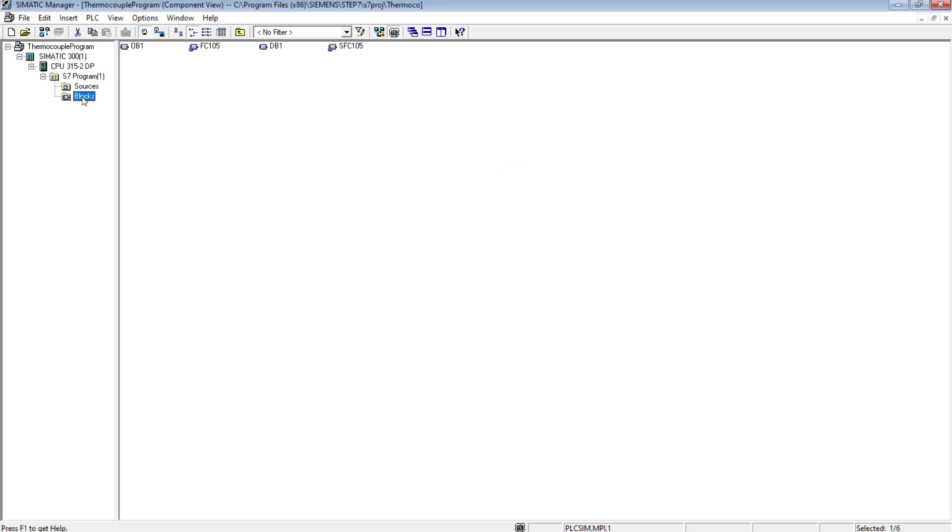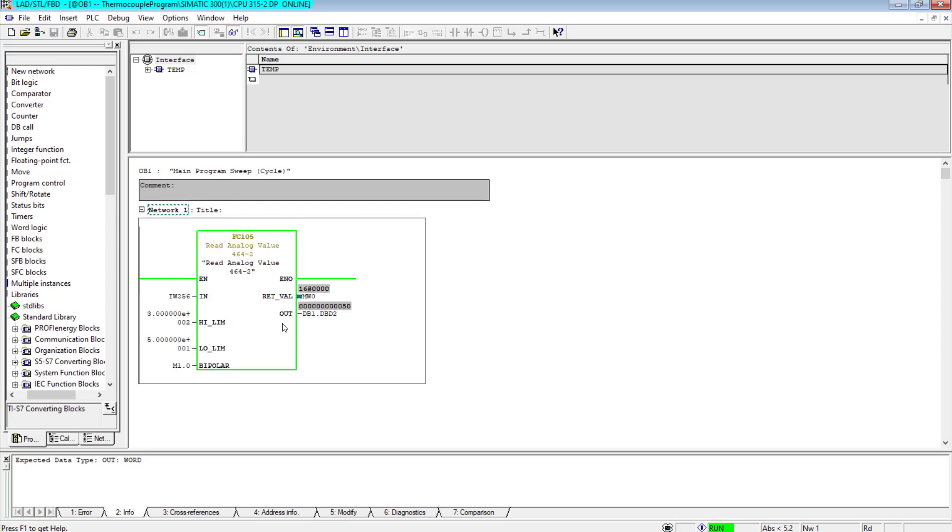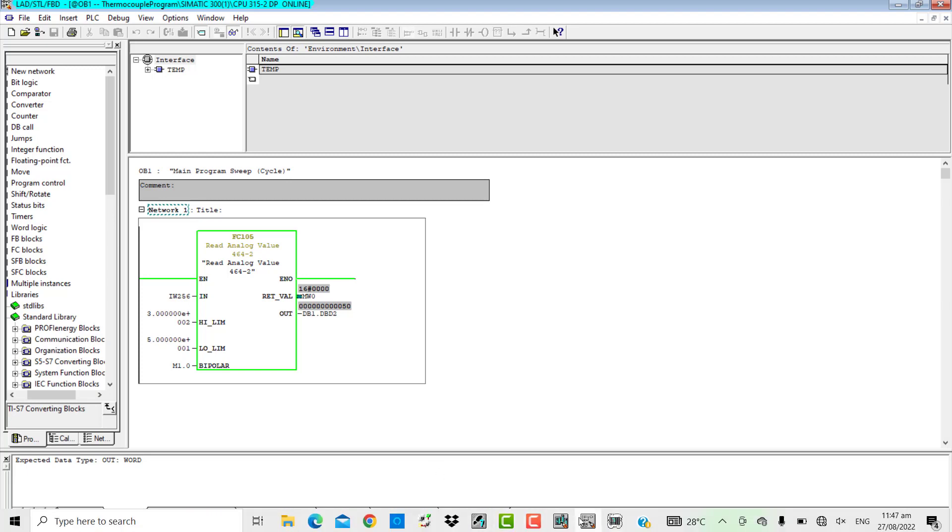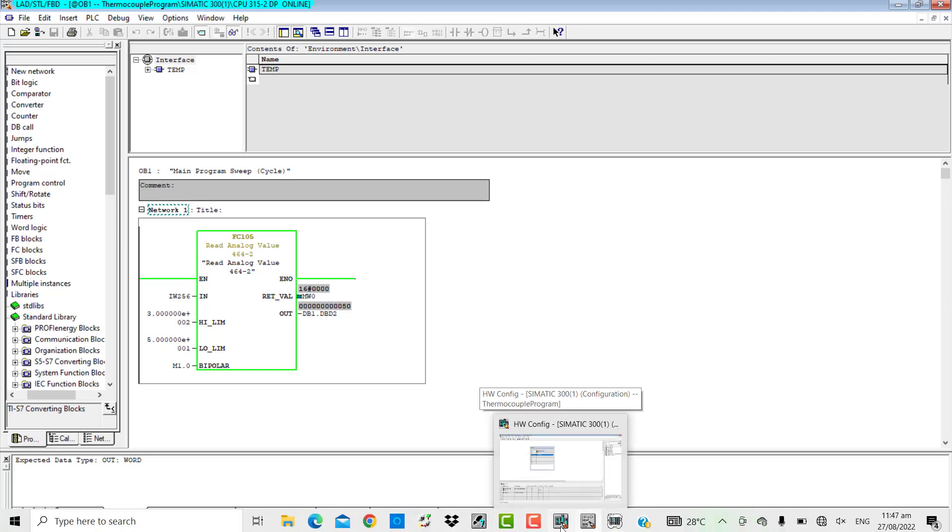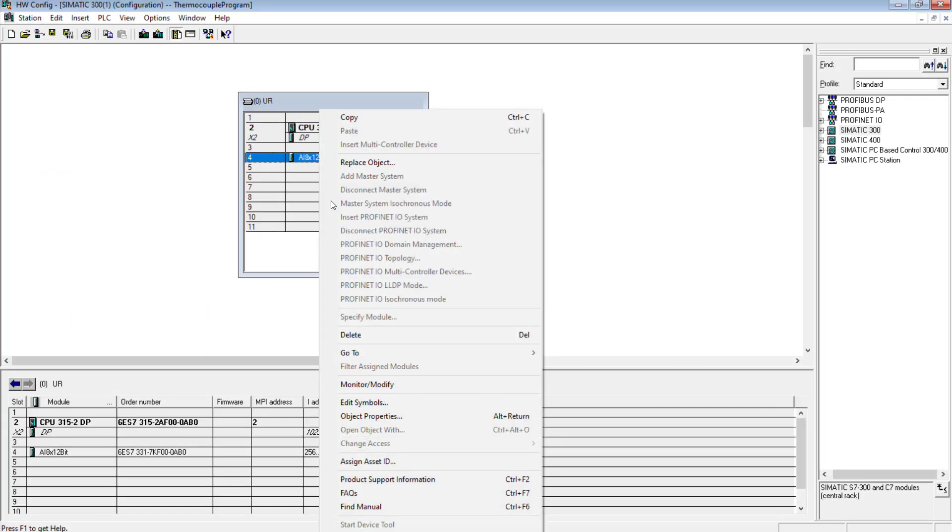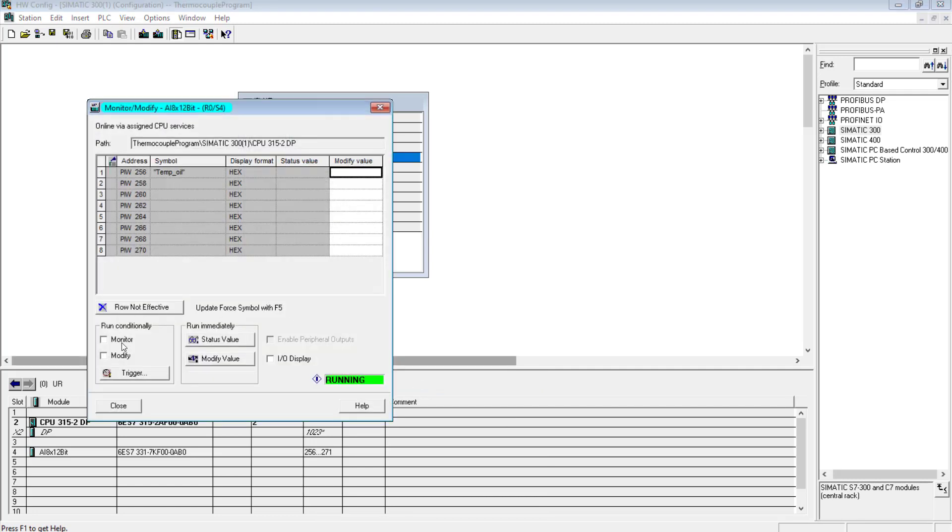After switching to run mode, now I'll open the OB1 and will try to monitor the PLC program. Now the 50 value has been shown. It is because the minimum scaling value is 50 and the field value now is 0 - sorry, 4 milliampere in this case, because the range of the analog input card is 4 to 20 milliampere and 4 to 20 milliampere are being output by the temperature controller as well.